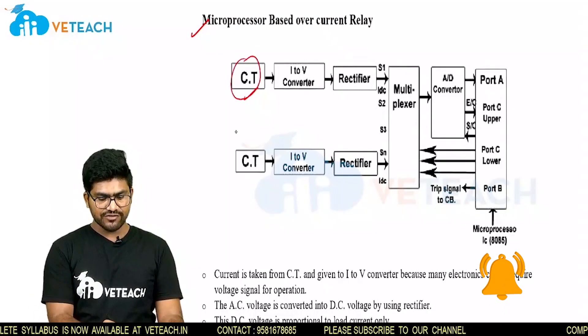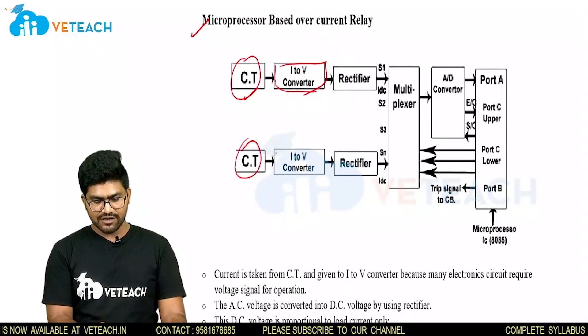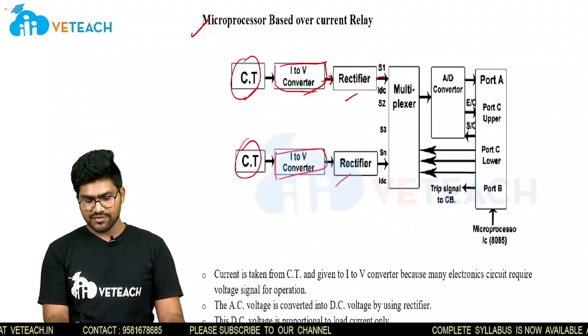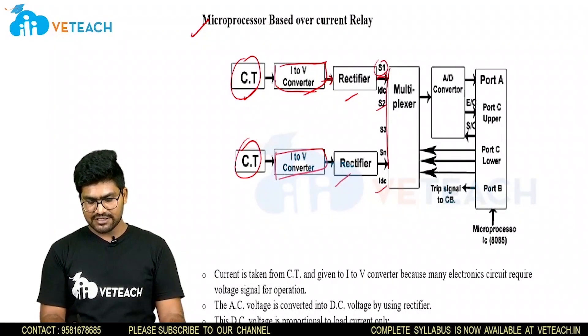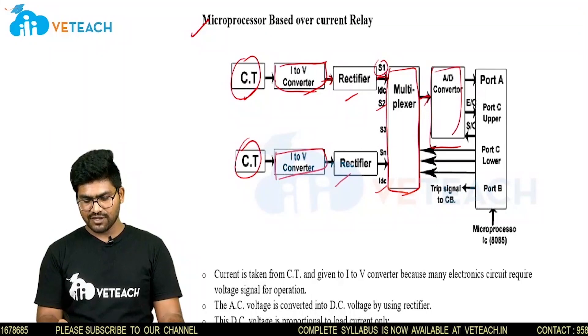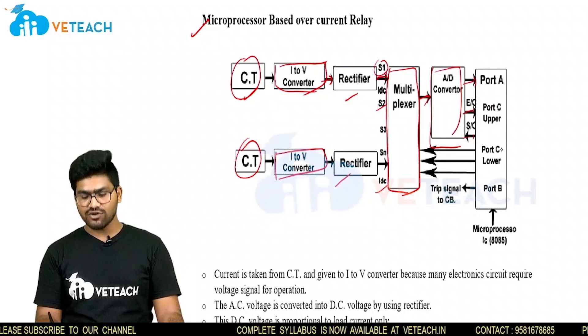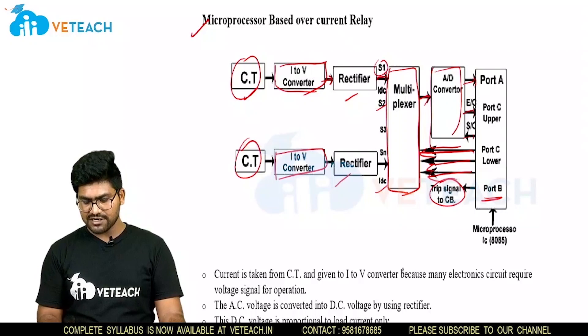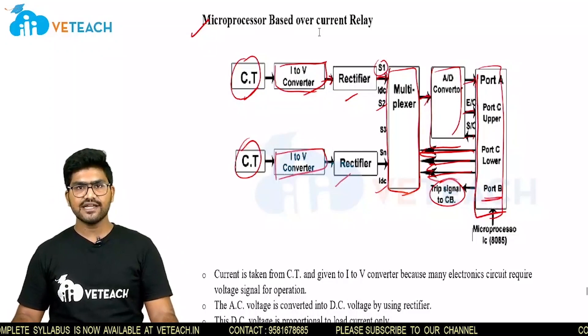Here from two CTs we have taken CT1 and CT2. From there I have an I to V converter, and here also an I to V converter. This voltage is given to a rectifier in both cases, and from here we are getting IDC S1, IDC S2, and IDC. This is given to a multiplexer, which is then connected to an A to D converter at port A. E by C, S by C, upper port C, and from port C lower we are again feeding back to the multiplexer. Port B will give the trip signal to the circuit breaker. This entire part is the microprocessor, which is IC 8085.